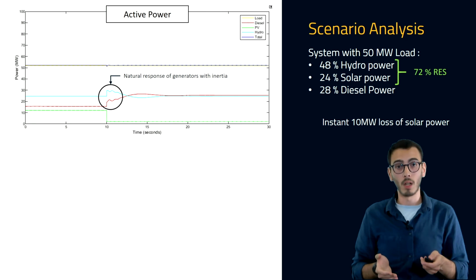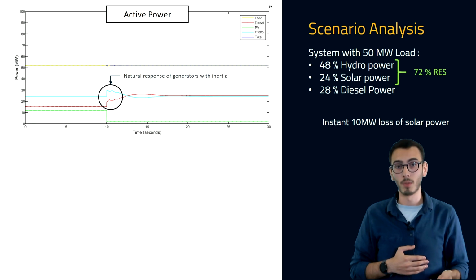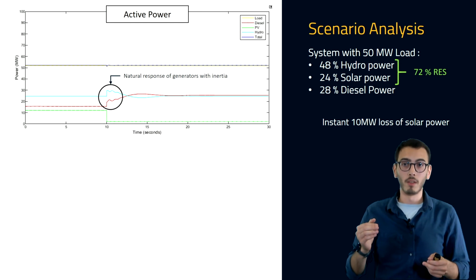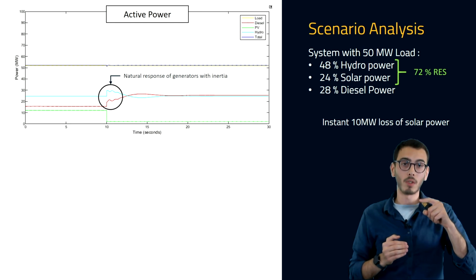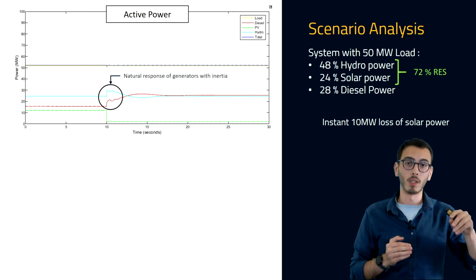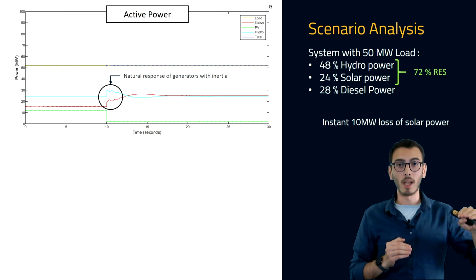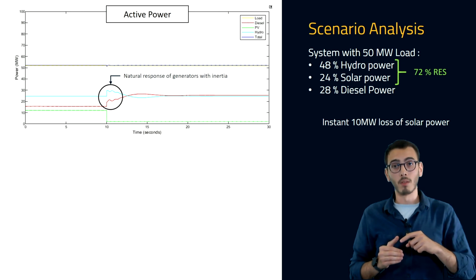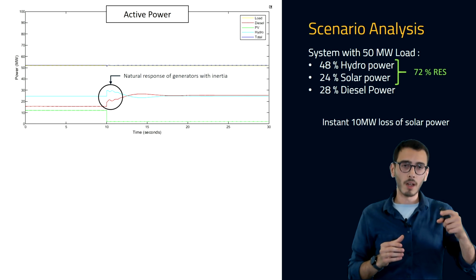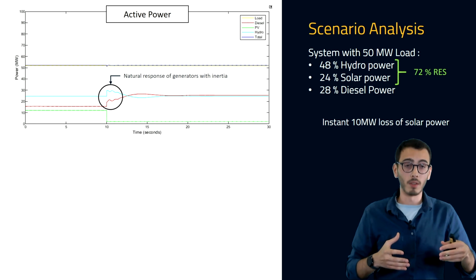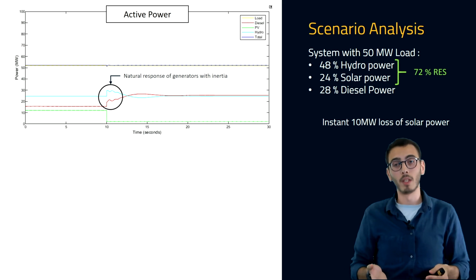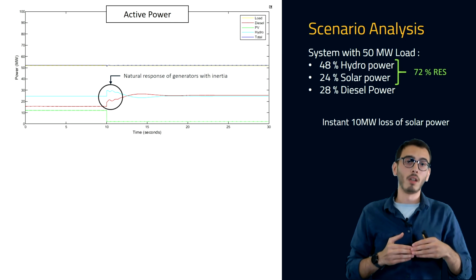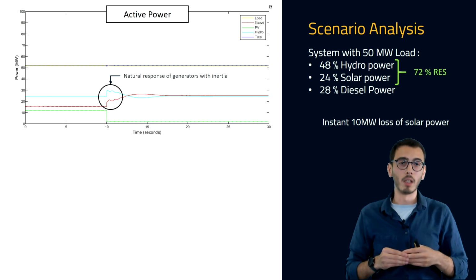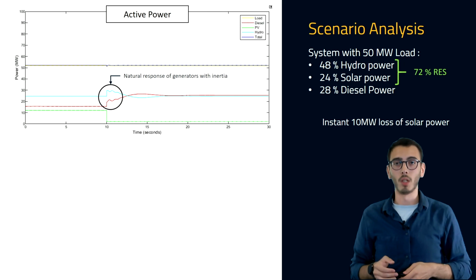And as we can see, for hydroelectricity, they do not provide primary reserve, as I said. So the power is going to peak because of inertia, and then it's going to go down again to the value that it had before. For the diesel generator, it peaks, and then after some time the diesel generator is actually going to provide the power that is needed, and is going to re-establish the equilibrium between demand and generation.